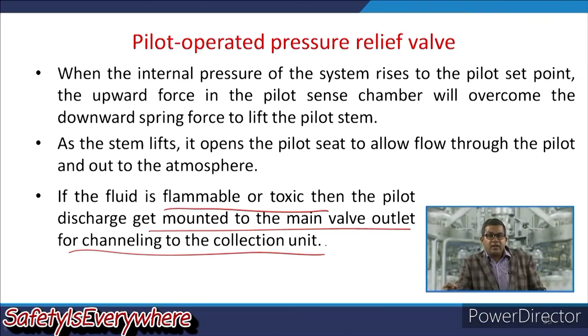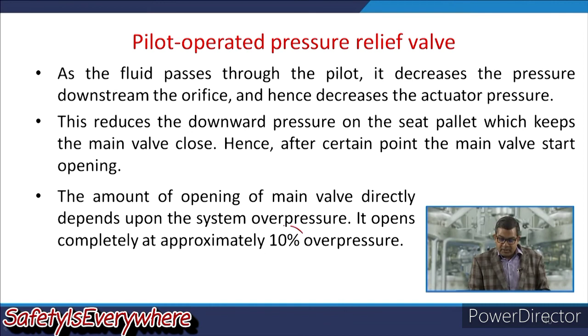As the fluid passes through the pilot, it decreases the pressure downstream of the orifice, and hence decreases the actuator pressure. This reduces the downward pressure on the seat pallet, which had kept the main valve closed. So after a certain point, the main valve starts opening. The amount of opening of the main valve directly depends on the system overpressure, and it opens completely at approximately 10% overpressure.